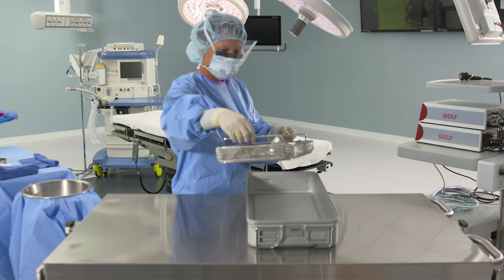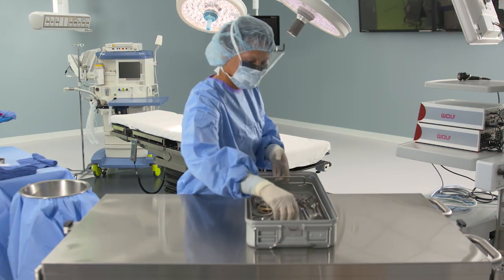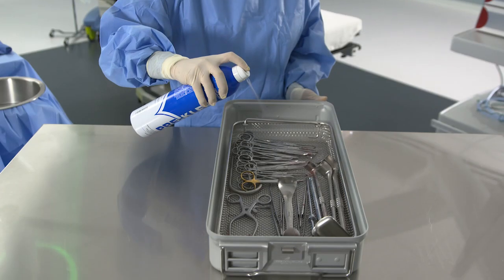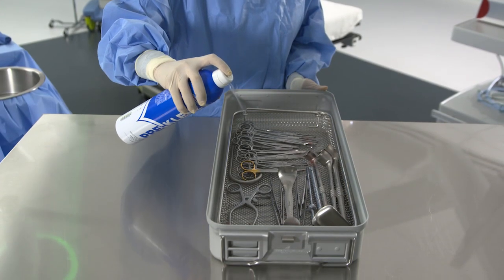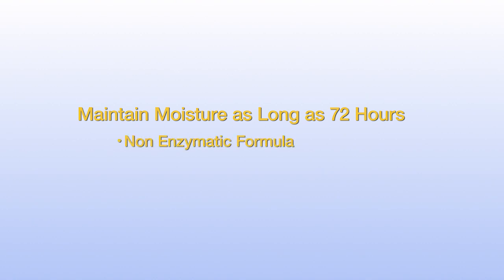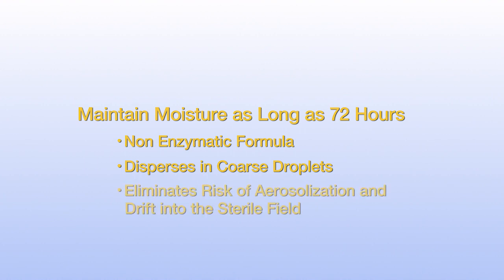Pre-Klenz point-of-use processing gel allows staff to initiate the pre-cleaning process without handling contaminated instruments. The formulation maintains the moisture and pliability of soils for extended periods, even as long as 72 hours. Pre-Klenz point-of-use processing gel is a non-enzymatic formula that dispenses in coarse droplets, which eliminates the risk of aerosolization and drifting into the sterile field.